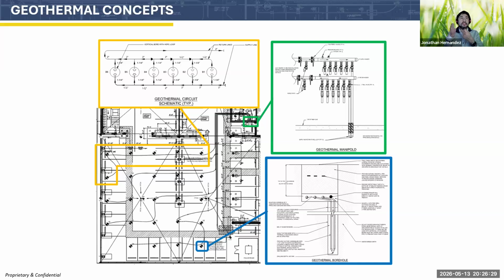It's designed via a manifold that you see in the green box, and the circuits there are 6, 8, 10, 12 boreholes long. The reason for that is either A, you need circuits for both heating and cooling simultaneously, especially if you're going to be doing load management, load sharing among other users, such as a thermal energy network. But also, it provides that redundancy.